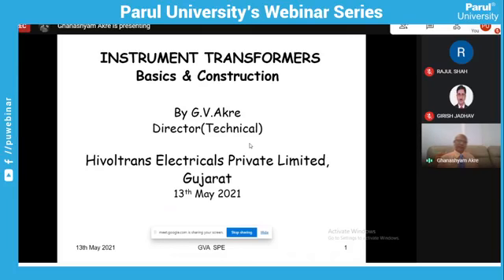Now, whenever there is a system like that, we need to have two things. One is the measurement of the energy which is being transmitted and traded. And second is the protection of the complete system. These two most vital things require sensors. That 765 kV, you cannot sense it by any instrument here. We have to reduce that 765 kV or 400 kV or 220 kV to a very low measurable voltage. As per standard, it is 110 volt. Similarly, the very high currents flowing in thousands of amperes also have to be reduced to a measurable limit, and that is 1 ampere or 5 ampere.